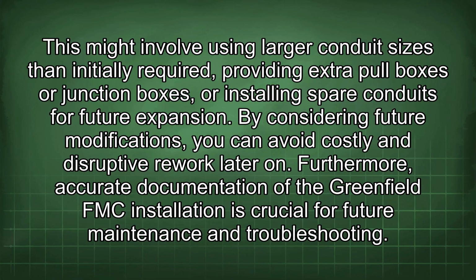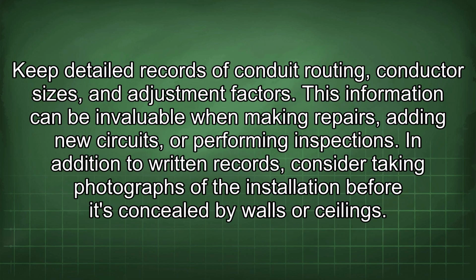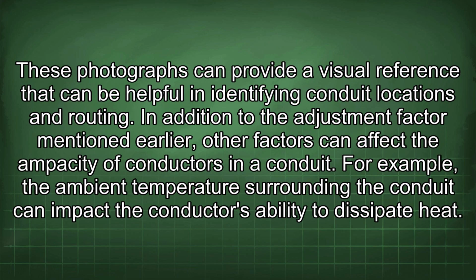Furthermore, accurate documentation of the Greenfield FMC installation is crucial for future maintenance and troubleshooting. Keep detailed records of conduit routing, conductor sizes, and adjustment factors. This information can be invaluable when making repairs, adding new circuits, or performing inspections. In addition to written records, consider taking photographs of the installation before it's concealed by walls or ceilings. These photographs can provide a visual reference that can be helpful in identifying conduit locations and routing.